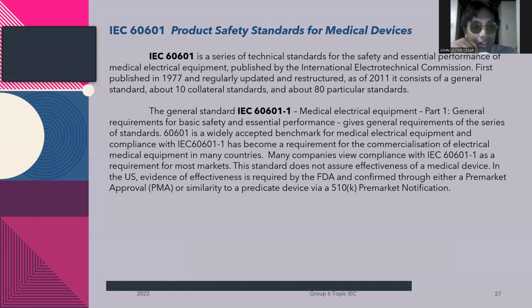the series of standards. 60601 is a widely accepted benchmark for medical electrical equipment, and compliance with IEC 60601 Part 1 has become a requirement for commercialization of electrical medical equipment in many countries. Many companies view compliance with IEC 60601 Part 1 as a requirement for most markets. This standard does not assure effectiveness of the medical device. In the US, evidence of effectiveness is required by the FDA and confirmed through either a pre-market approval (PMA) or similarity to a predicate device via 510(k) pre-market notification.